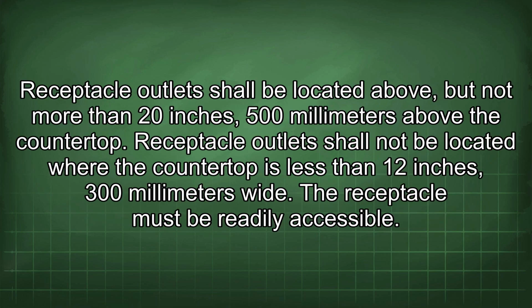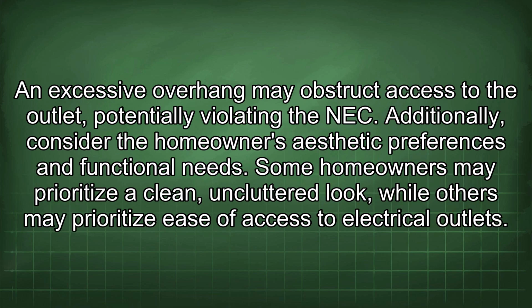The receptacle outlet shall be located above, but not more than 20 inches (500 mm) above, the countertop. It shall not be located where the countertop is less than 12 inches (300 mm) wide. The receptacle must be readily accessible—an excessive overhang may obstruct access to the outlet, potentially violating the NEC.